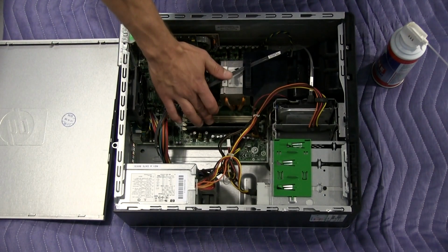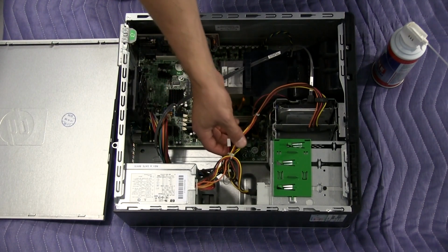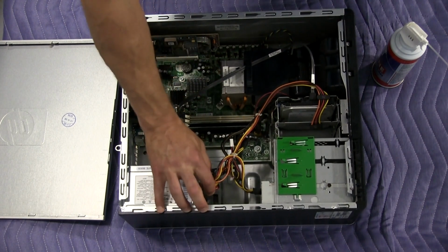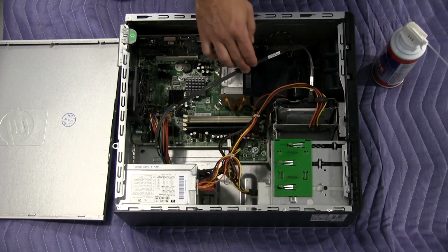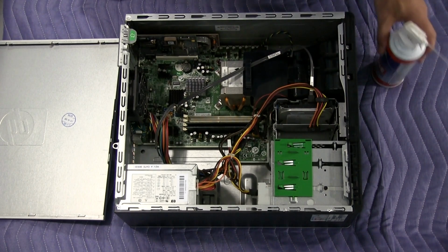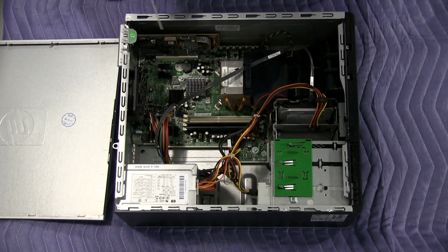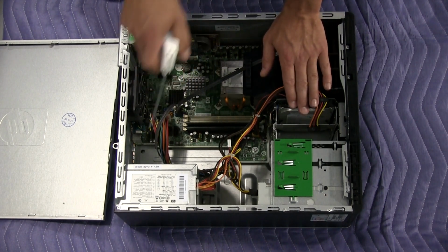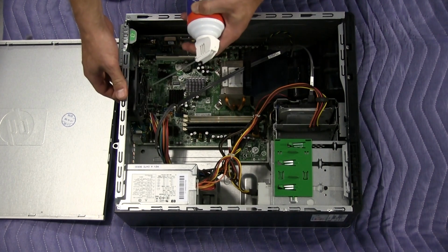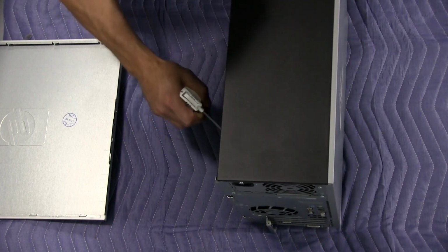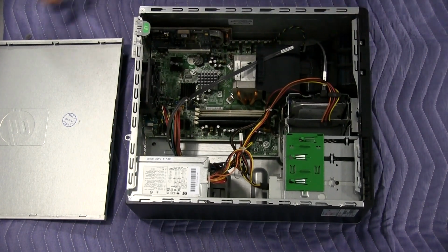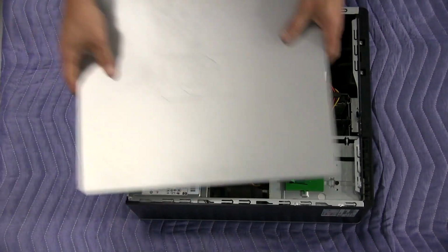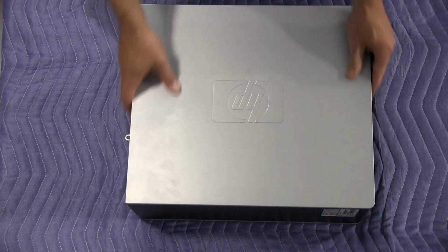First, I'd like to make sure that all my circuit board connections are secure, all my cables are secure, all the way throughout the system. And then with a static-free vacuum and/or an aerosol can, we can start to spray off and get any dust or debris. When the host PC maintenance is complete, just reassemble the panel and attach back to your machine.